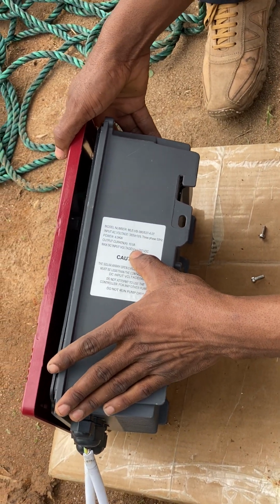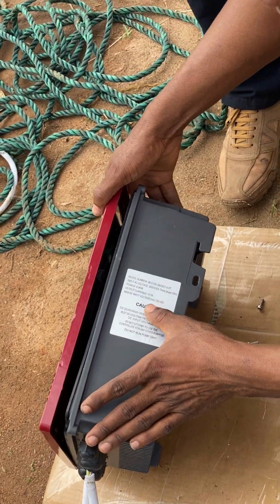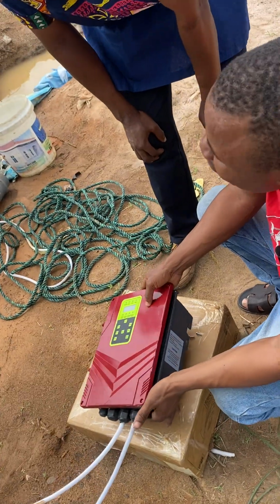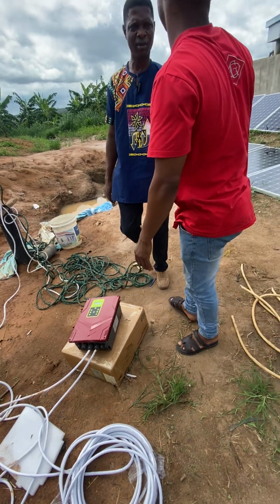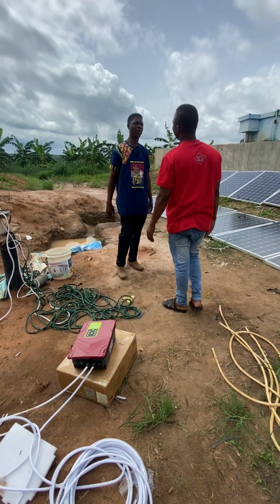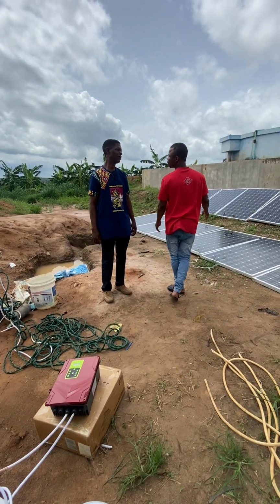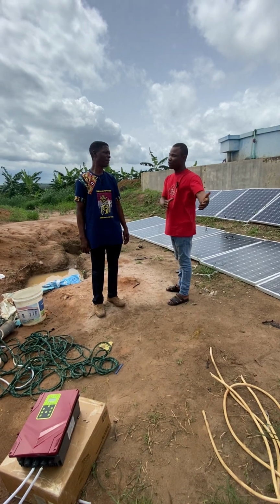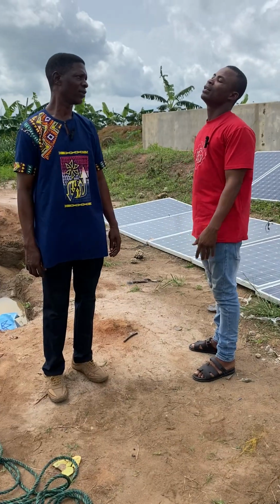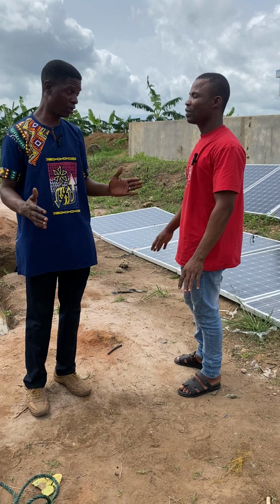See, now it should not exceed 750 volts, while we are doing 500 or something volts. You understand, we're doing 500 or something volts with that 48 volts times 12, which gives us 570 something volts. So at least between 500 volts to 750 volts, it will be in between.